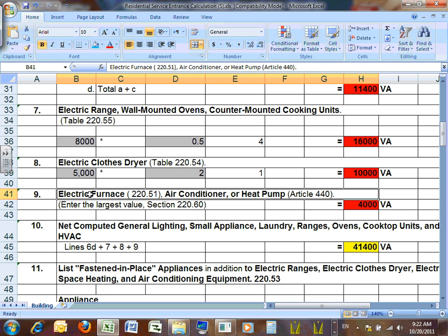I made the decision that I have three stairways based on a rule. 3 times 3 is 9 kW for the stairway heaters, plus the heating element from the gas, which is not a whole lot. Compare this to the cooling. The cooling is 4 times 4, which is 16. So which one is larger, the heating or the cooling, in this case?